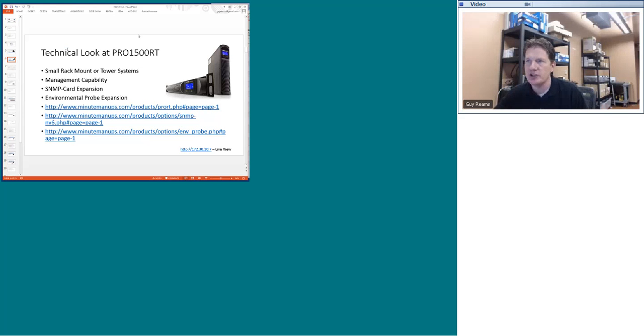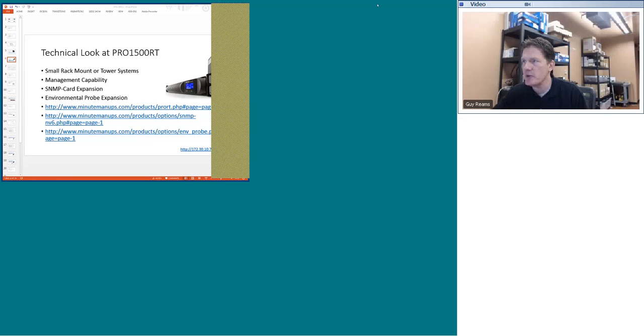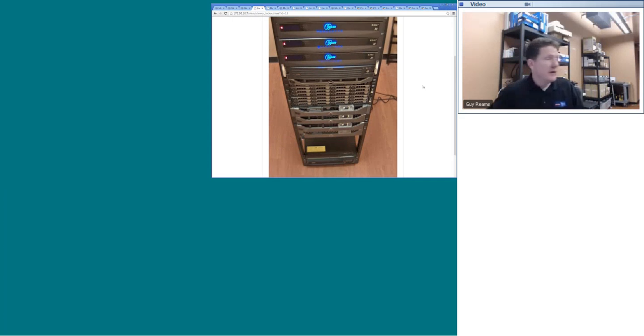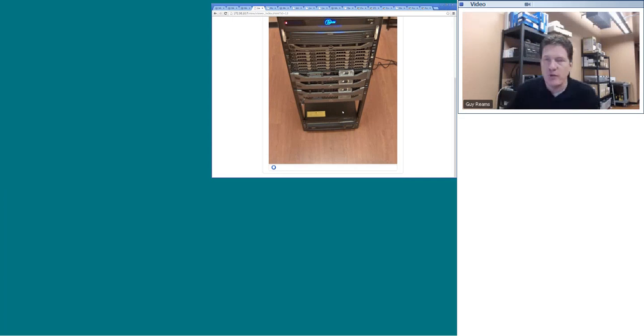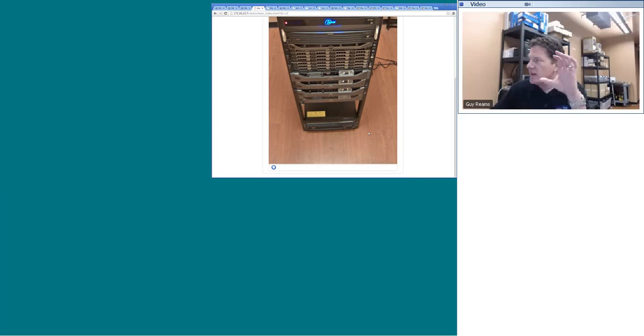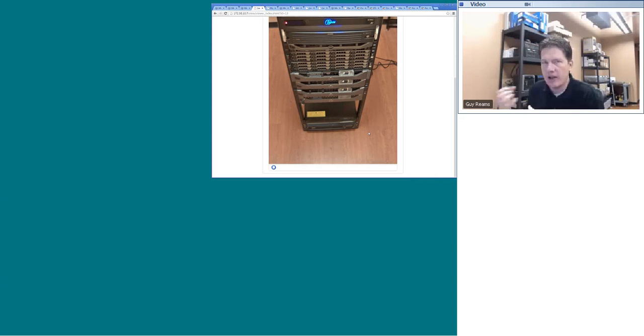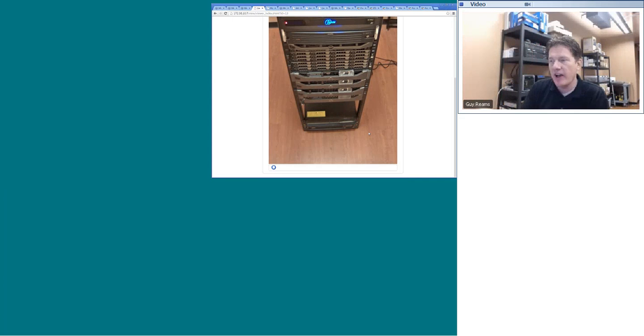The environmental probe allows you to monitor temperature and humidity in the server room and alert if one of those becomes an issue. This also provides an SNMP trap. If you're not into SNMP, you should be — you'll have SNMP software that manages your customers and alerts you when things go awry. The SNMP card you plug into this UPS gives you that ability. Looking at a live view of my server room, down at the bottom is the Minuteman UPS. Hit one of the buttons and the LCD lights up showing input voltage and any alerts. It will warn you if there's too much draw — if you plug too many devices in, you'll hear a loud squealing sound. It fits very nicely into a single telecommunications rack-style mount.